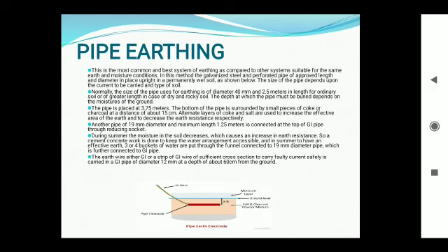The earth wire, either GI or strip of GI wires of sufficient cross-sectional area to carry the fault current safely, is carried in a GI pipe of diameter of 12 mm at a depth of about 60 cm from the ground.